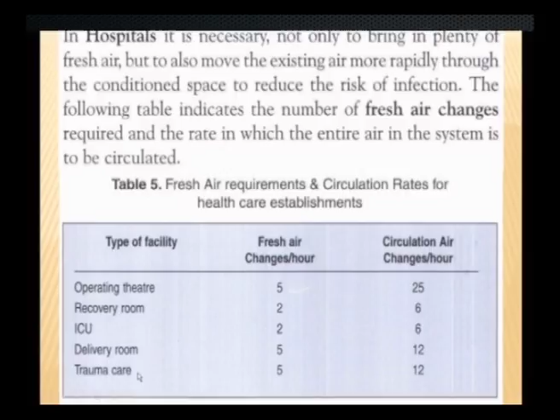So, one air change is described as completely taking out whatever air volume is inside the room and replacing it with completely fresh air. You need to do that 5 times per hour for an operating theatre. Similarly, for a delivery room and trauma care, it is the same. When it comes to recovery and ICU rooms, you need to do it 2 times.